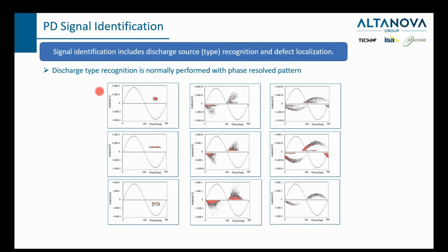So the operator should be able to refer to the library to see what type of defect we're looking at. One note here is that for different equipment or different apparatus, the phase resolved pattern will have its unique features. For example, if we're talking about GIS or motors or transformers, the phase resolved pattern will be quite different. Motor discharge has a lot of sub patterns. For example, in our database, we include 8 typical sub patterns for motors and generators. For GIS, I believe we have 4 or 5 sub patterns. For transformers, we have 7 sub patterns. So those are all site topics that require a lot of experience and knowledge to recognize the type of defects.